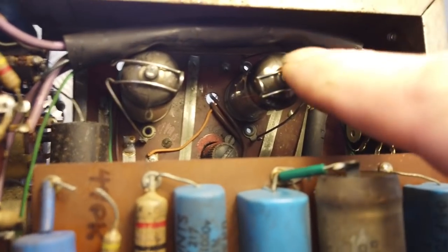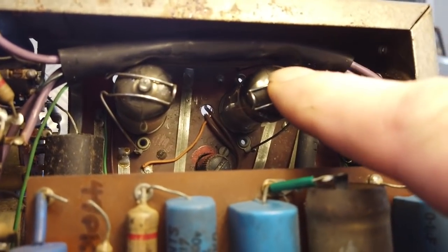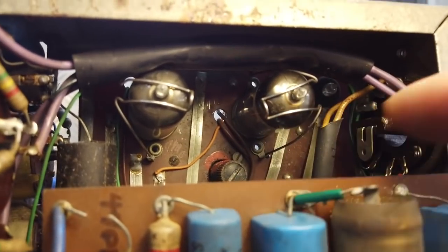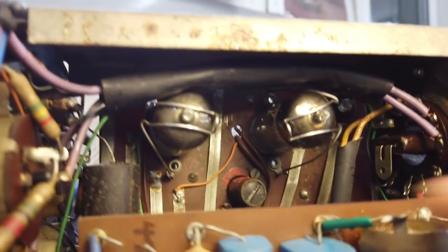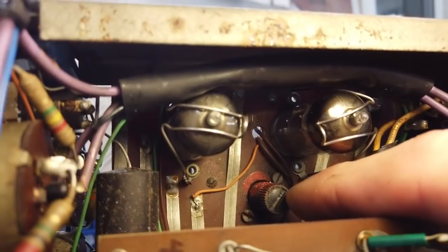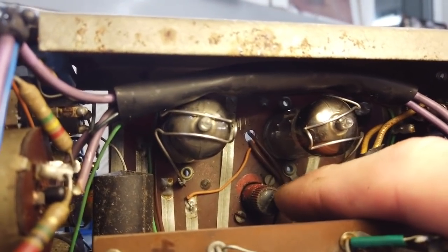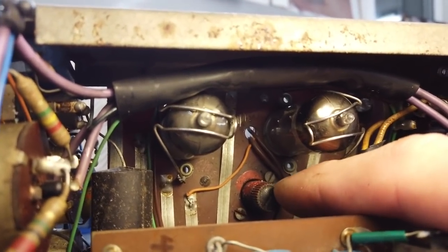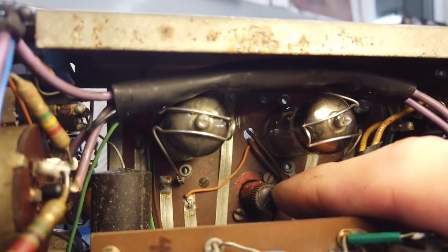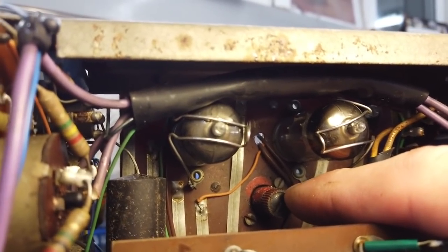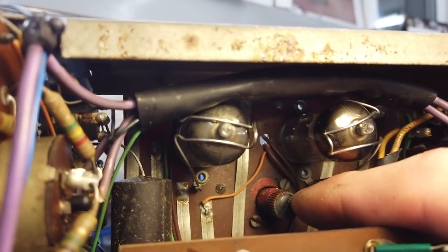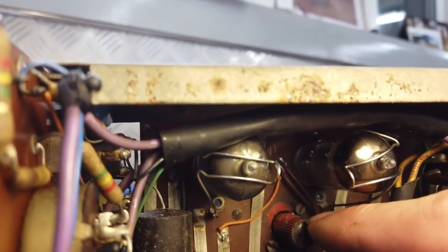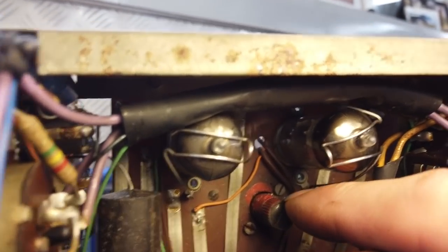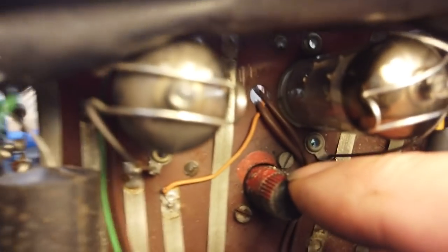So I think these perhaps are controlling the beam, which means that board at the bottom is something to do with the beam. And indeed, I can see a variable resistor here, like a volume control knob if you will, which could well be to do with fine-tuning the focus, or fine-tuning the brightness, or whatever it is. It's set, and you can adjust it, but it's factory set and marked with some paint.